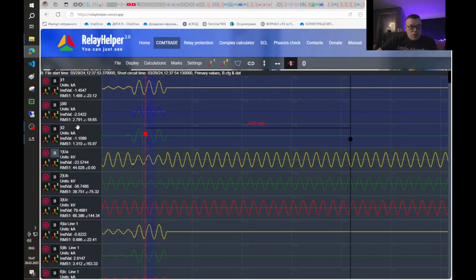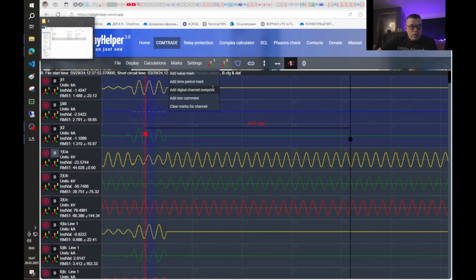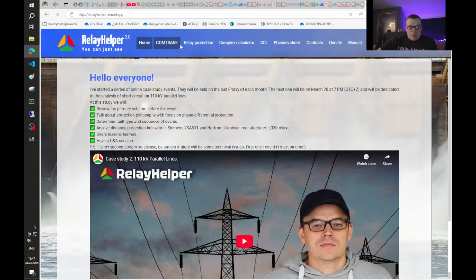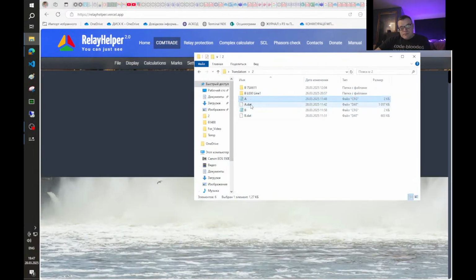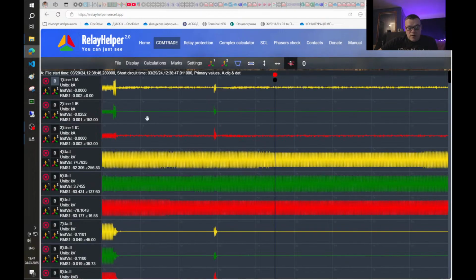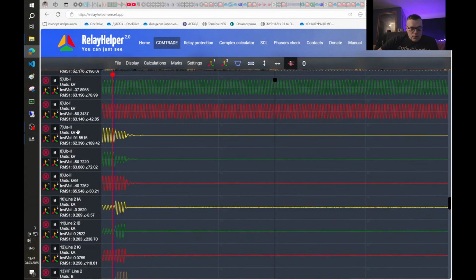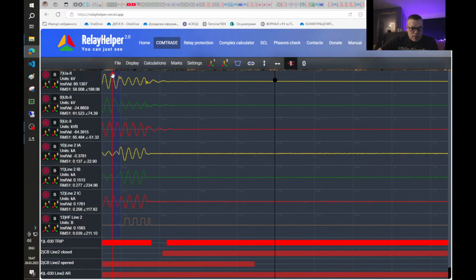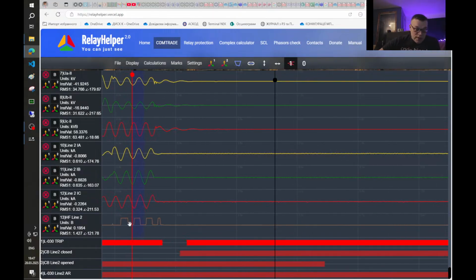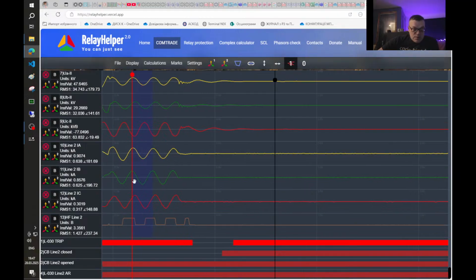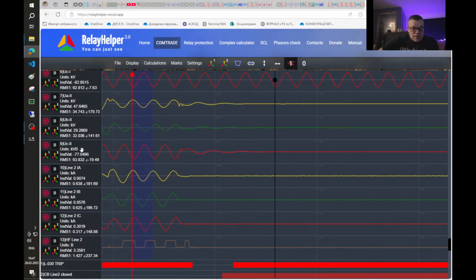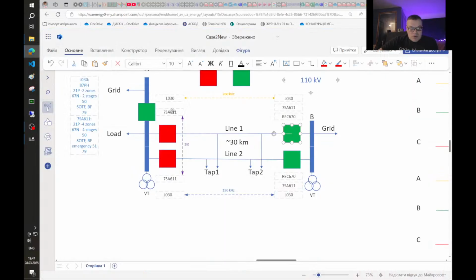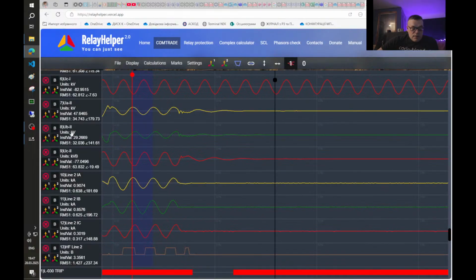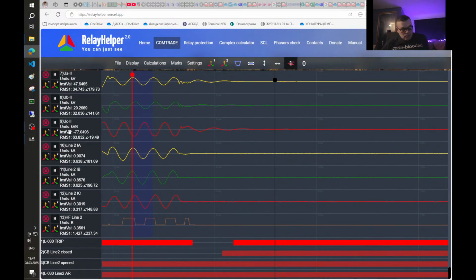So let's check what happened from the substation A side. From substation A, we don't have any records. So first, let's check phase differential protection, because we can see that there are pulses, but also that the current from the substation B side is much smaller. So first, let's calculate whether phase differential protection can work.